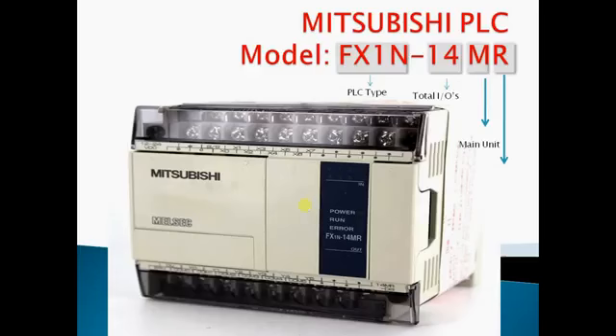And M represents main unit. It means that it has an inbuilt integrated power supply, CPU, inputs, outputs. And R represents output type. R means relay output and T means transistor output.